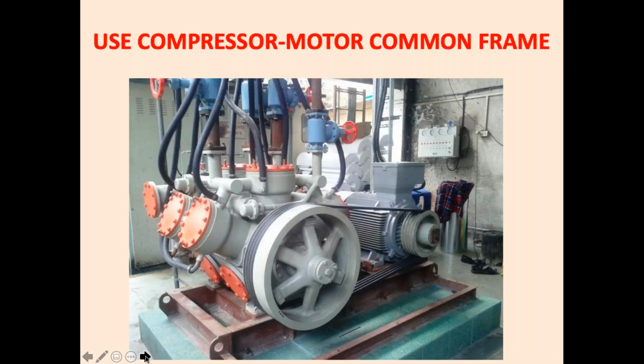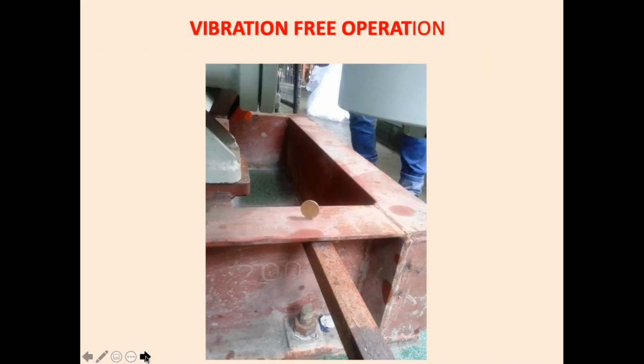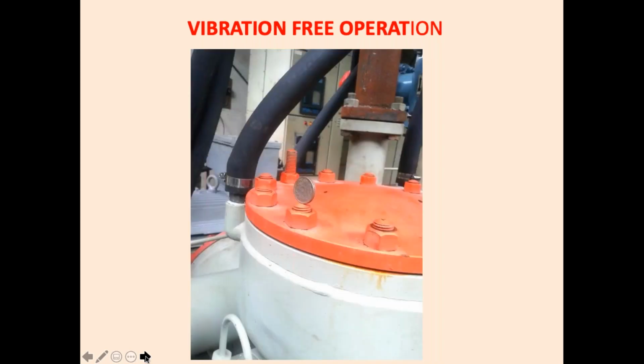This is an installation using a compressor motor frame by the manufacturer, and the alignment issues then get eliminated. Your shaft seal leakage problems will be eliminated, and you will have a very vibration-free installation. You can see that this is an operating compressor. You can keep a coin on a reciprocating compressor. It is not falling down. On the cylinder head also, this is a compressor in operation.